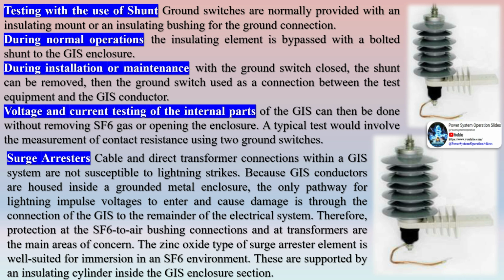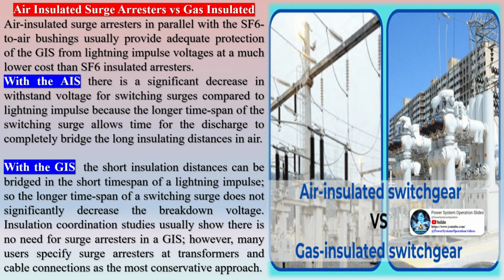During installation or maintenance with the ground switch closed, the shunt can be removed, then the ground switch used as a connection between the test equipment and the GIS conductor. Voltage and current testing of the internal parts of the GIS can then be done without removing SF6 gas or opening the enclosure. A typical test would involve the measurement of contact resistance using two ground switches.